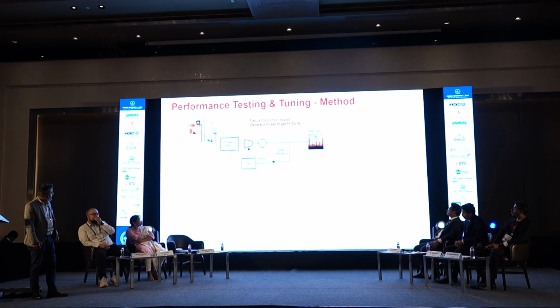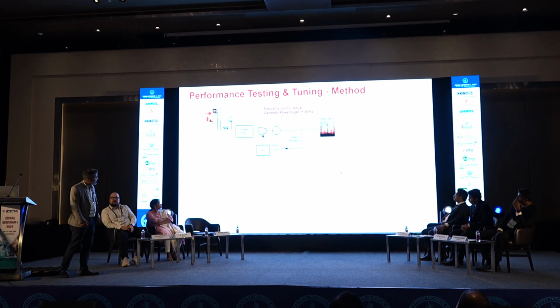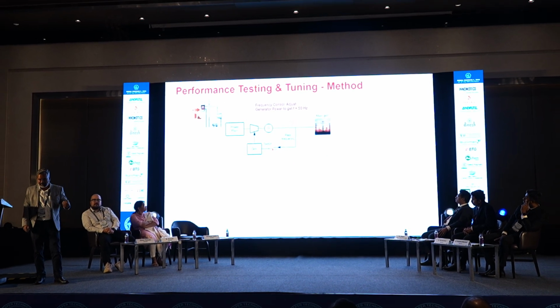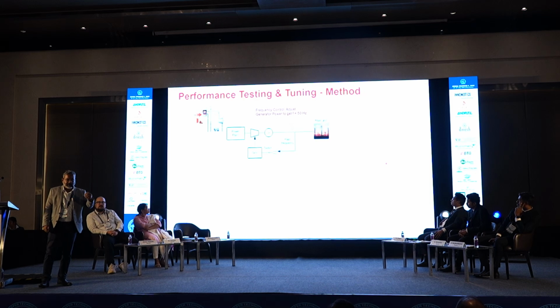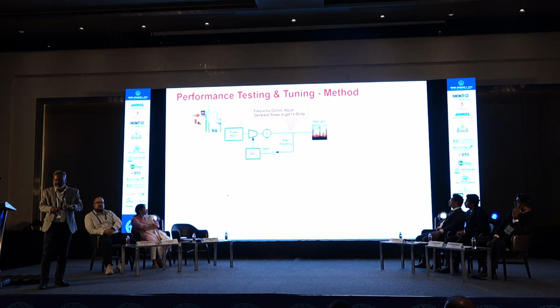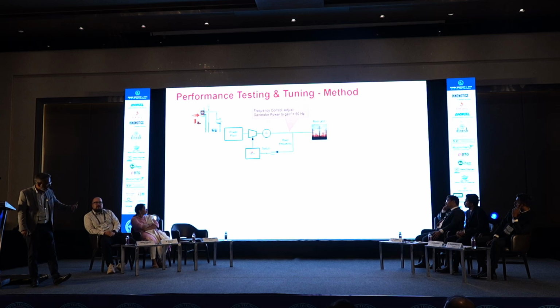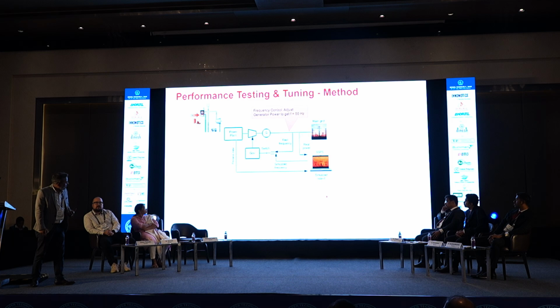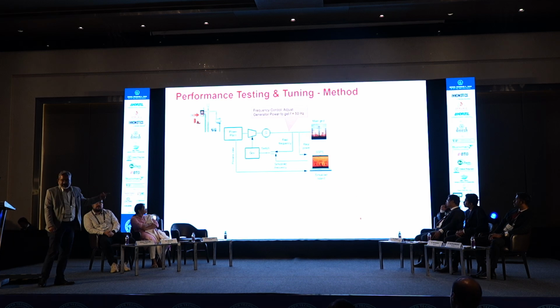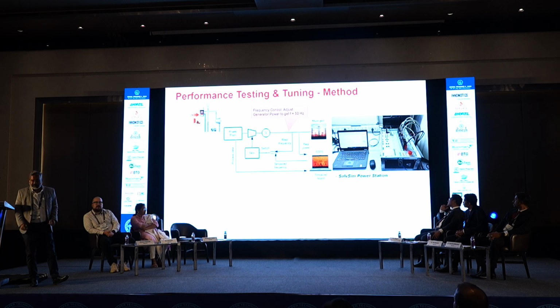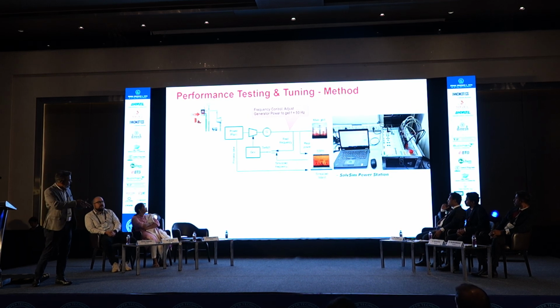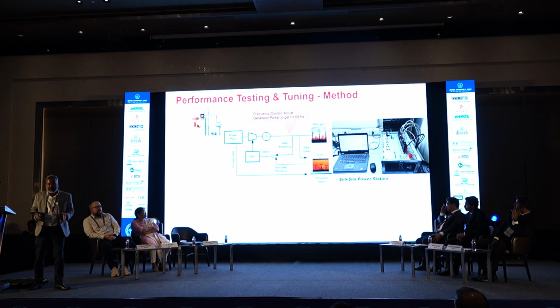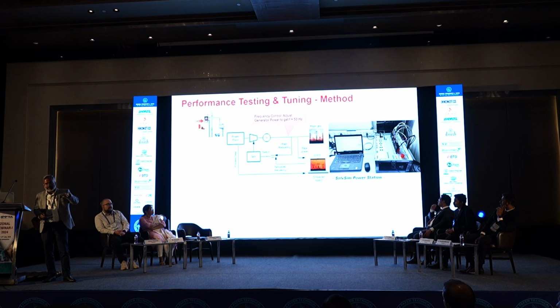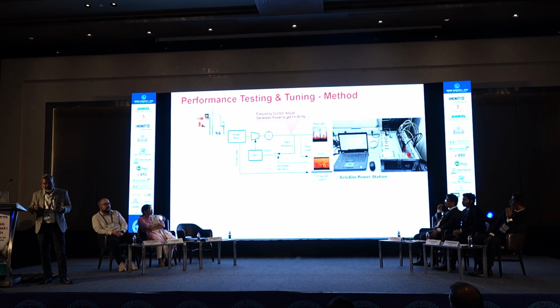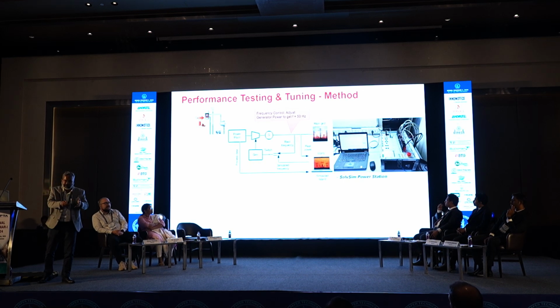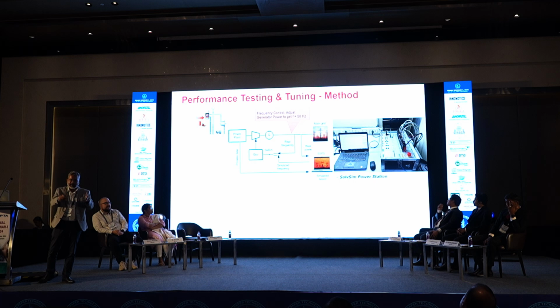So I just wanted to show you, normally the power plant with turbine generator system is connected to the main grid, and the governor senses the real frequency. Based on the changes in the real frequency, the governor responds to change in the megawatt output. This is the normal operation. But when the plant goes into an islanded situation, how we test it is we replace the real frequency with the simulated frequency from our testing kit. We inject the simulated frequency through the testing kit, by which we connect the governor, and then we give the load steps, as in an islanded system when some of the loads are getting disconnected or some of the loads are getting connected. So we discuss all those scenarios which come up in the plant and we see.